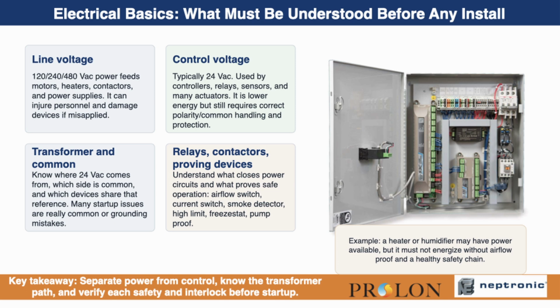Beyond voltage levels, the team must understand transformer paths, commons, interlocks, safeties, relay logic, and the difference between powering a device and commanding a device. A startup should never begin until the electrical path is understood. Safe and disciplined electrical verification is not optional. It is a core part of successful commissioning.